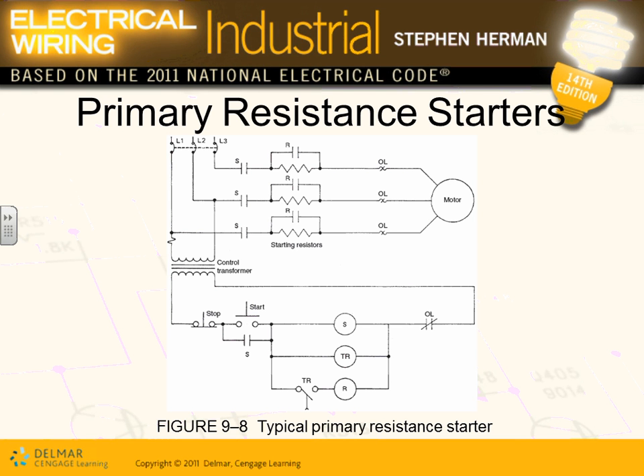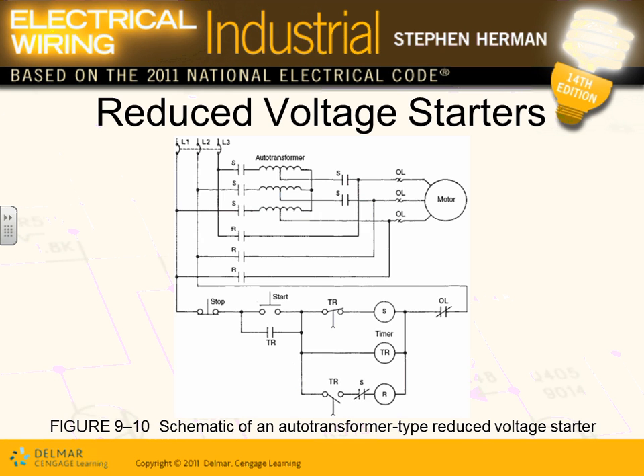480, knock it down to 240 for 10 seconds. The starting current goes down. I don't dim my lights when I start my motor. After 10 seconds, the control system, the timer, times out. This will close. Bam, bam, bam. You shunt these resistors. You basically have a path around them, and you have full voltage across your motor, and your motor is up and running. So that's your starting. That's voltage reduction.